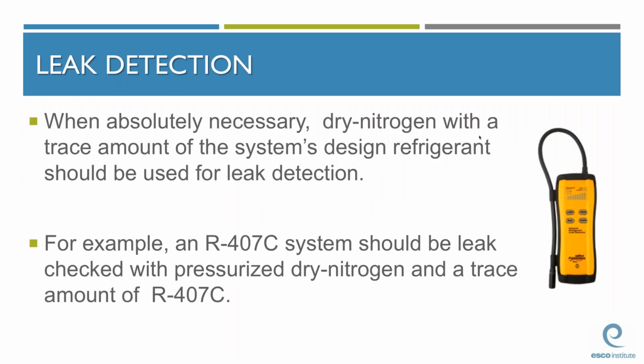When necessary, a trace amount of the system's design refrigerant can be added to the dry nitrogen to aid in the leak detection process. Adding this trace gas allows the technician to use an electronic leak detector on the system, but again, the leak detector must be capable of picking up the refrigerant that's been added as the trace. So the trace gas will be the same as the system refrigerant. So for example, an R407C system can be leak checked with pressurized dry nitrogen and a trace amount of R407C.